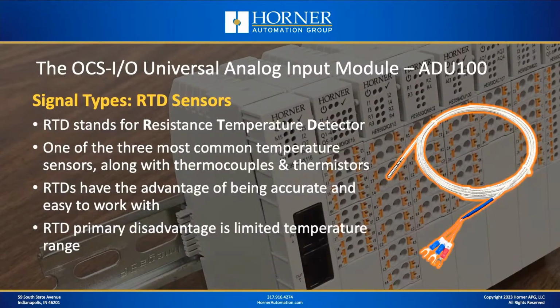Next, let's pivot and talk about RTD temperature sensors. RTDs stand for resistance temperature detector. They're definitely one of the most common temperature sensors that are out there, and today they're probably the preferred temperature sensor in most applications. That's because RTDs have several advantages. They're quite accurate, they're quite easy to work with, and nowadays they aren't really all that expensive. Early in my career, they had a reputation of being very pricey, but maybe with the proliferation and manufacturing upgrades, that's caused the cost of RTDs to come down.